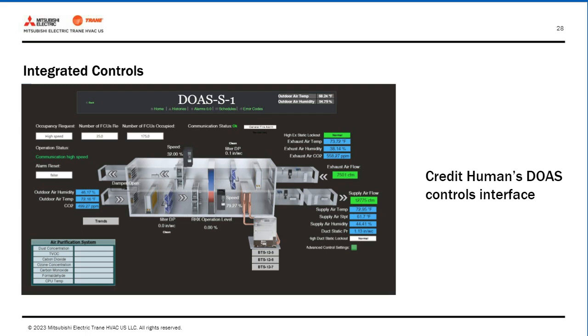What we see here is an example of one of the DOAS units on the roof, because this Credit Human tower has 2 of these DOAS units, a total of 30,000 CFM, 15,000 each, of fresh air coming into the building. These are conditions that we captured on an ordinary day last month. You can see exhaust air coming out of the building and out of the unit. The energy recovery wheel in the middle says RHX operation level at 0%. The wheel wasn't running that day because it just wasn't hot enough to transfer any of that cool air from the building to outside. Once it gets hotter, probably even on a day like today when it gets up to 80 degrees, that wheel will start running and transfer some of that heat to pre-treat the outside air coming into the building.